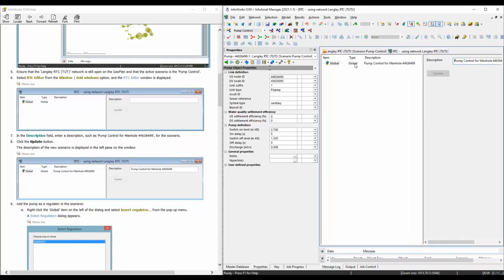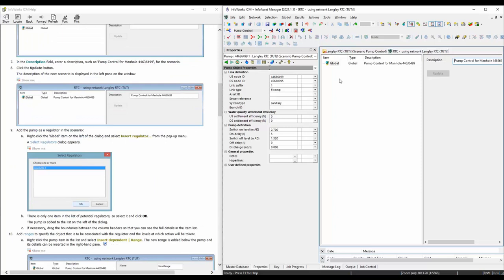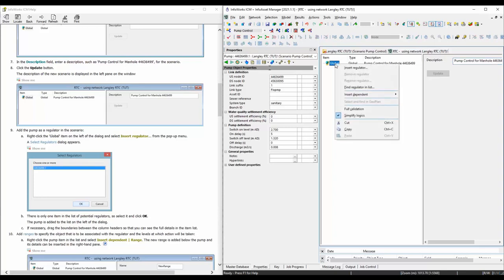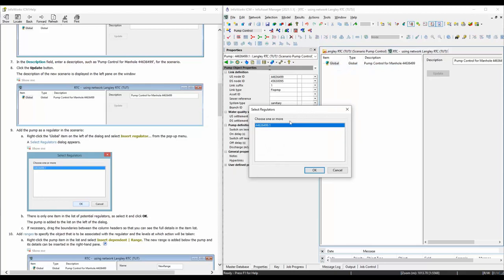What we want to do is turn the pump on at one level and turn the pump off at another level. To do that, we need to set up two ranges. One range: if the level in the wet well is less than 1.5, the lower range, the pump should be turned off. If the level is higher than that range, it should be turned on. We need to create those two ranges - a higher range and a lower range - and after that we're going to apply rules. First, we need to insert a regulator. A pump is one of the regulator types - so we hit OK and we have the fixed pump we're going to regulate.